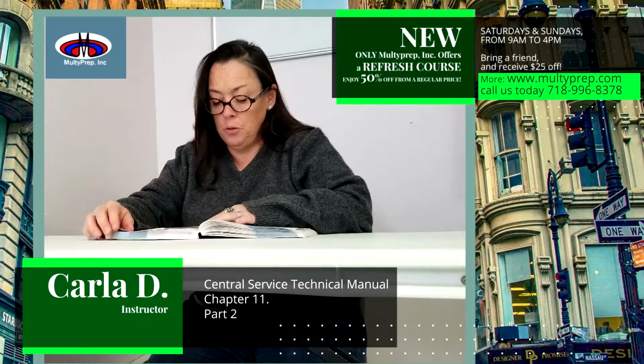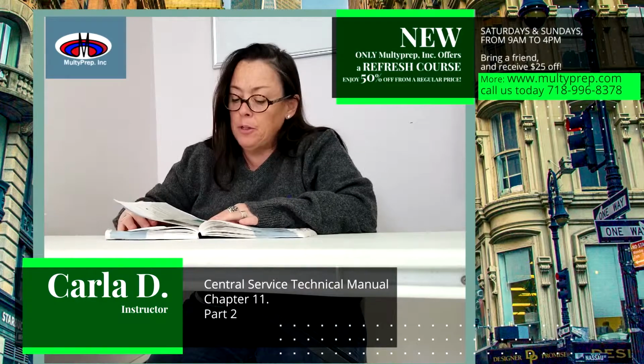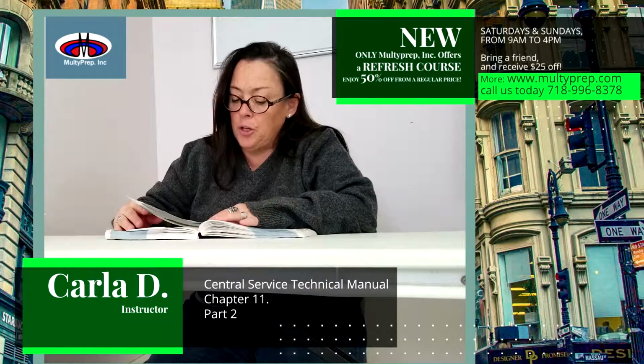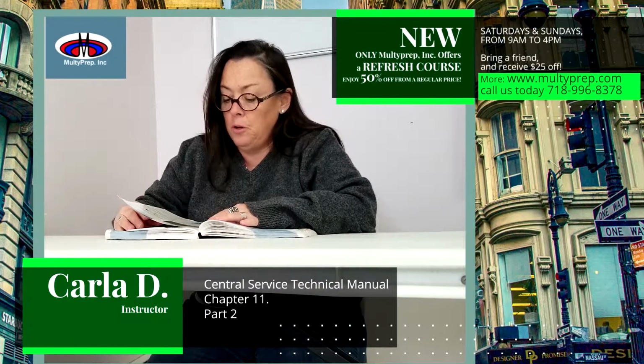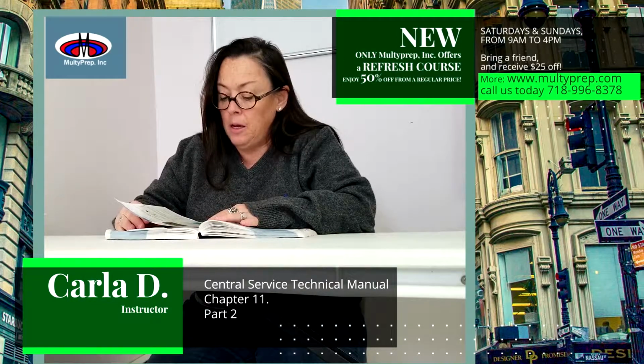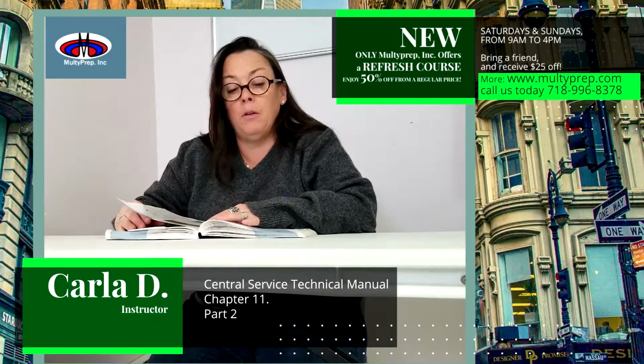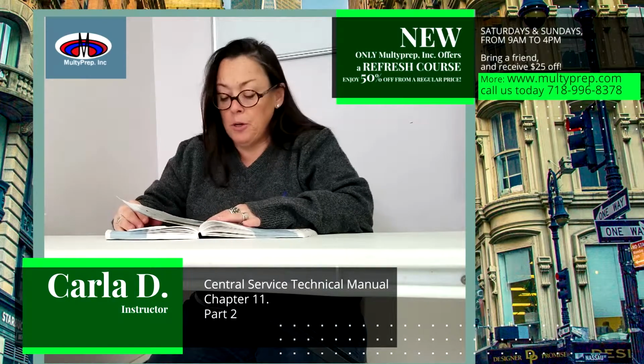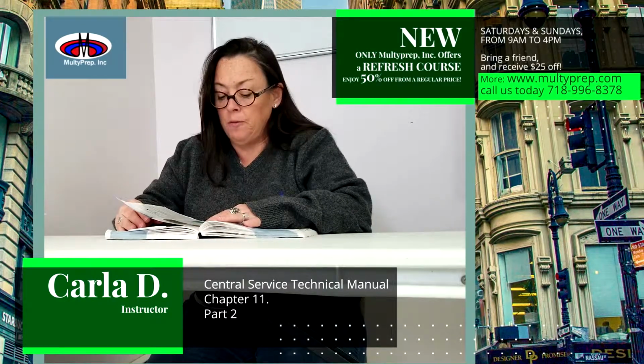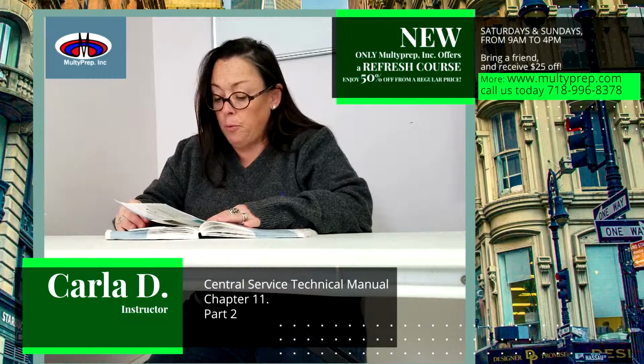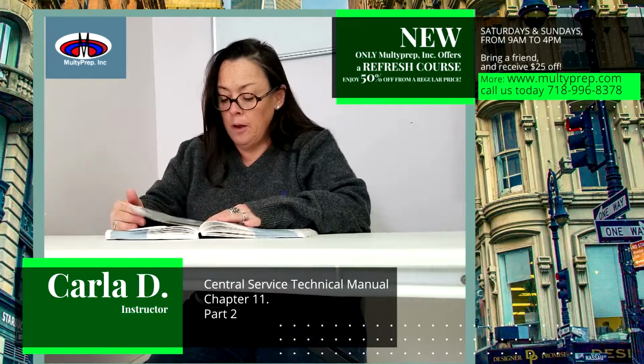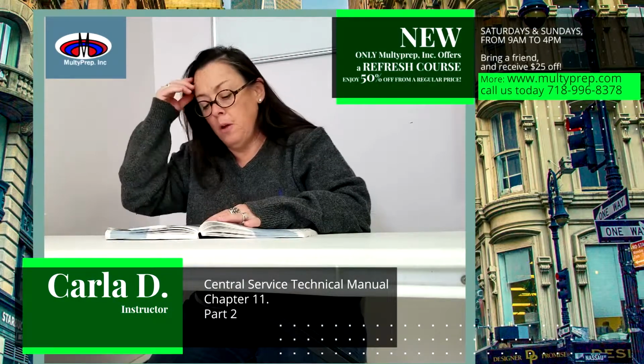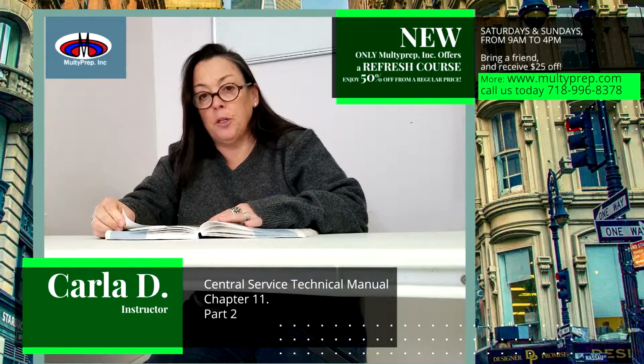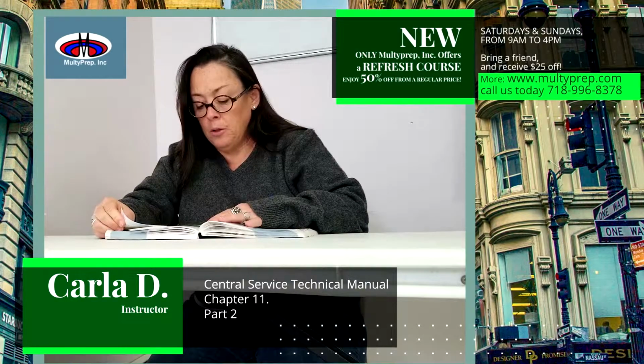Semi-rigid endoscopes. Semi-rigid endoscopes are termed as such because the shaft is made of very thin stainless steel, thus allowing it to bend slightly without kinking the metal. Semi-rigid endoscopes are primarily used in urology to view the bladder and the distal portion of the ureter. See Figure 11.32 for an example. While they have the ability to bend slightly more than a rigid scope, they will be damaged if too much pressure is applied or if they are bent beyond their intended limits.